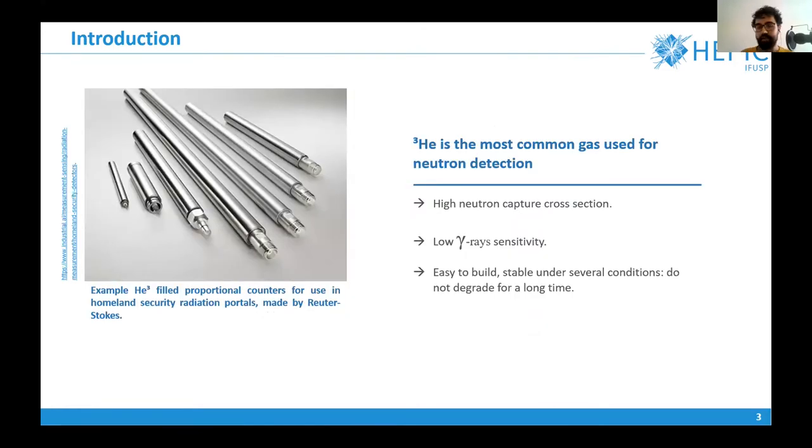Classically, the most common gas used for detecting neutrons is helium-3. Helium-3 has several advantages such as high neutron capture cross-section. It has low gamma ray sensitivity, which is nice also because you want to avoid the background radiation.